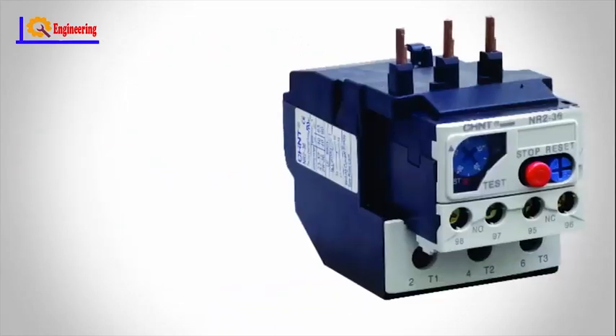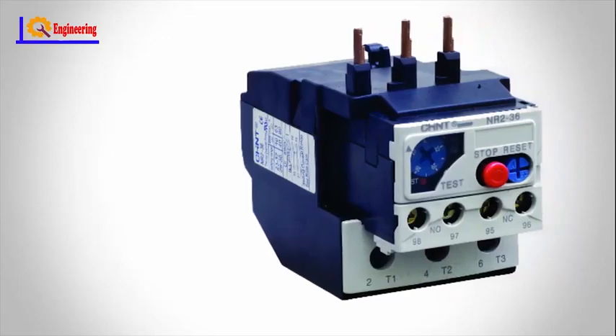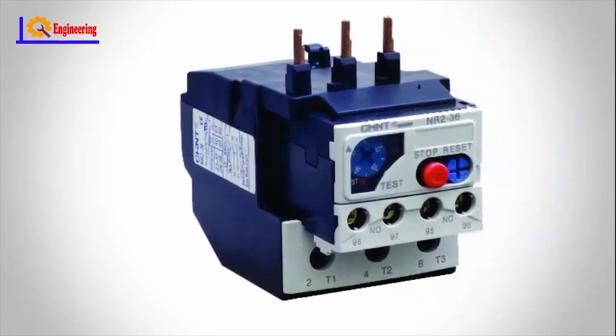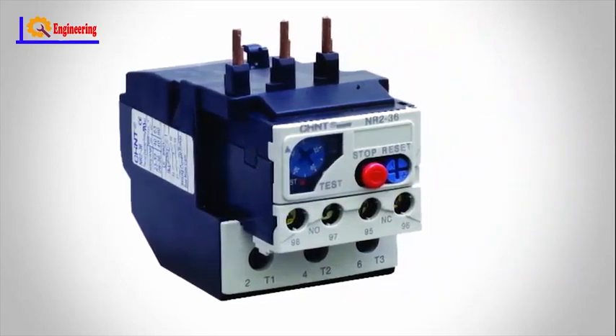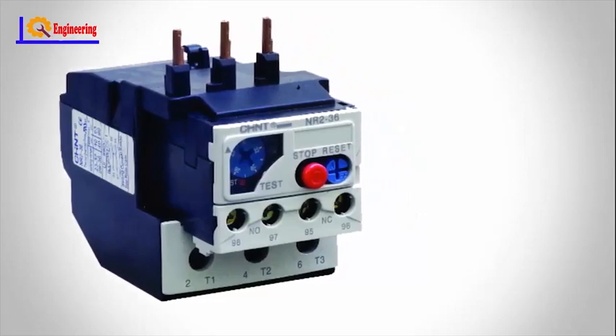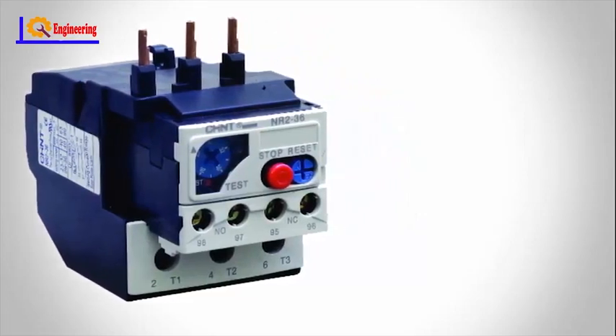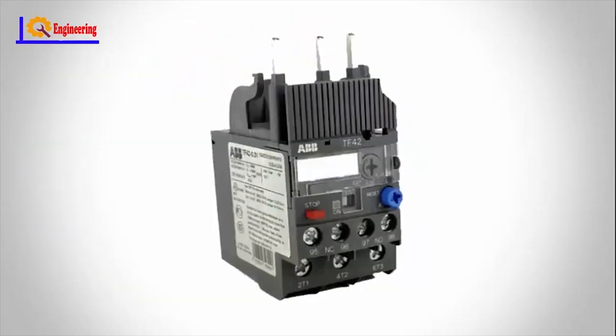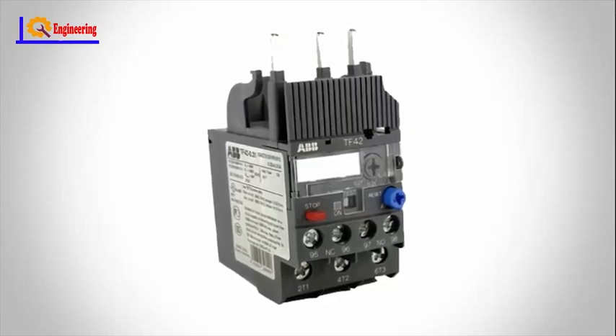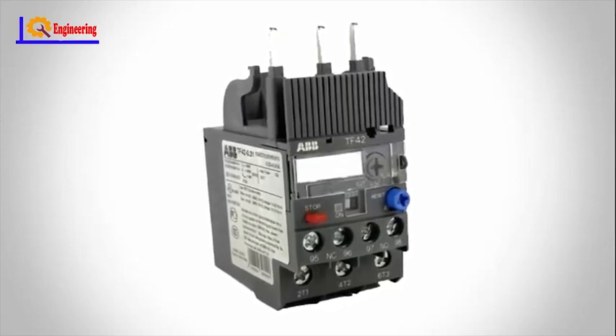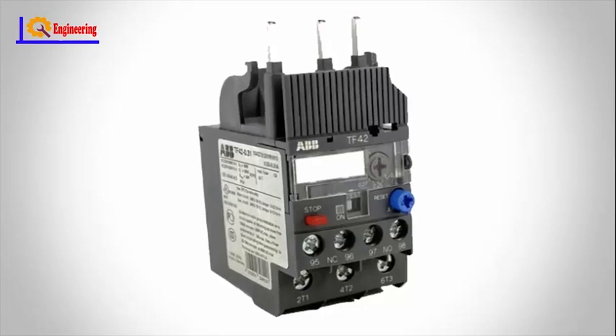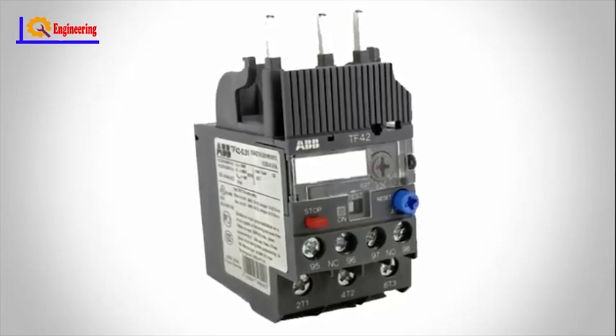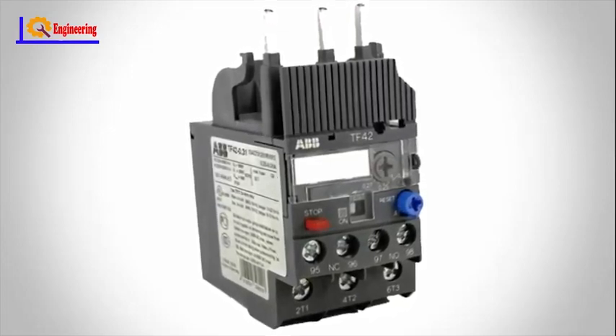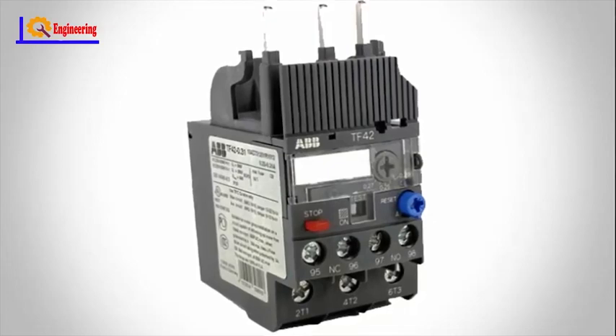Thermal relay. These relays are based on the effects of heat, which means a rise in the ambient temperature beyond the limit directs the contacts to switch from one position to the other. These are mainly used in motor protection and consist of bimetallic elements like temperature sensors as well as control elements. Thermal overload relays are the best examples of these relays.